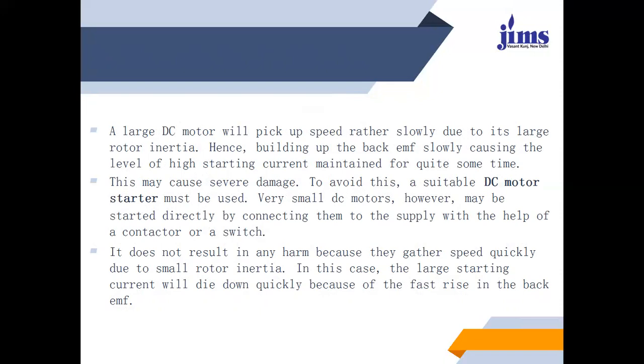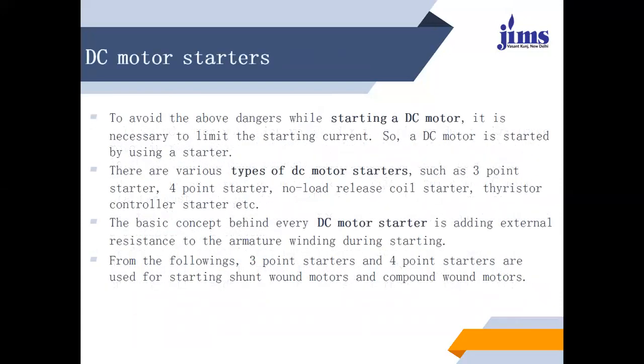Very small DC motors, however, may be started directly by connecting them to the supply with the help of a contactor or a switch. It does not result in any harm because they gather speed quickly due to small rotor inertia. In this case, the large starting current dies out quickly because of the fast rise in the back EMF. Now we will look at the starters for DC motors.